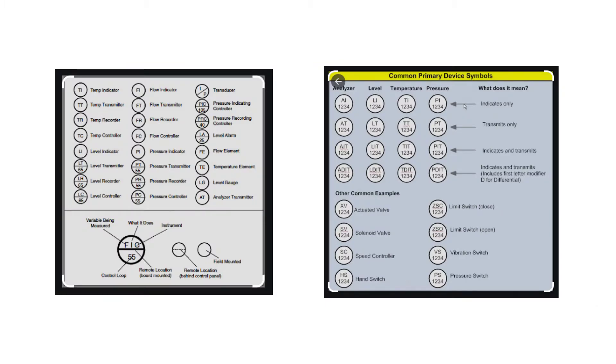Here we have the different type of tags that you'll see on a P&ID. One thing to keep in mind: if you see a horizontal line through the tag, through the round circle, that means it's a remote location. Board mounted is a solid horizontal line. Remote location with the dashed line is behind a control panel.